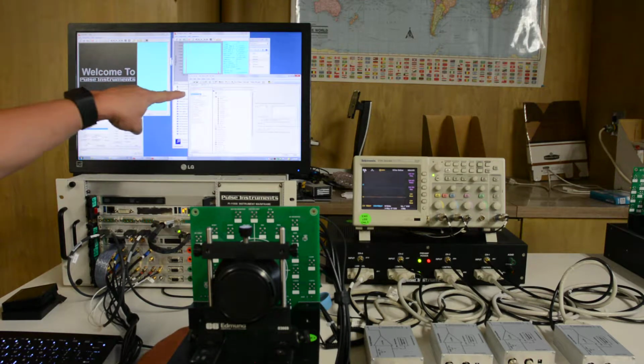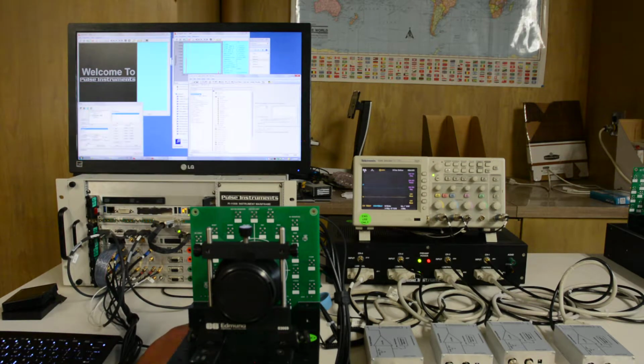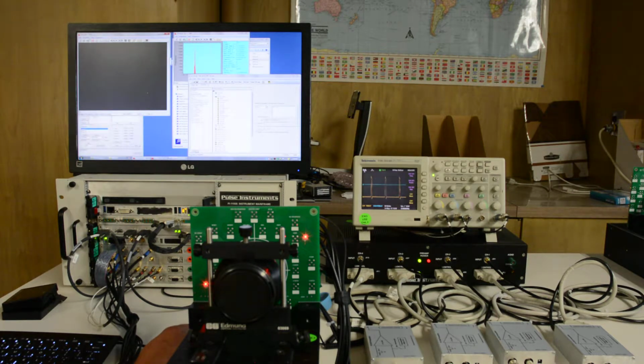I'll select the setup test plan, which contains all the settings for the biases, clock drivers, and timing files. I can have this display a setup page for the operator where I can select the output size, integration time, and the voltages for the two critical bias supplies. I'll go ahead and click OK.